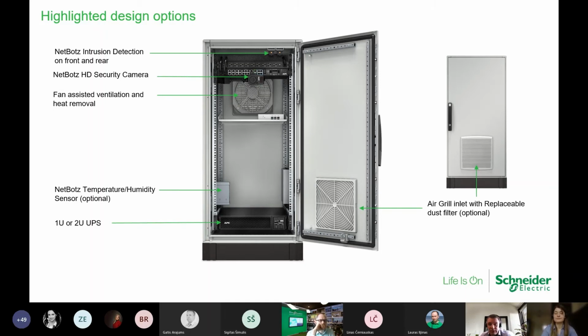Fan-assisted ventilation is the cooling option for this solution. We don't have active cooling here, and with this ventilation we can cool up to 2 kilowatts of IT load, which is basically the target for these applications.